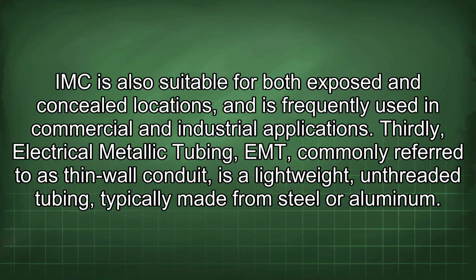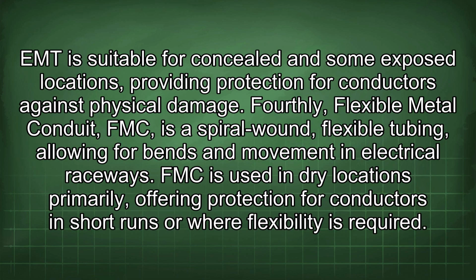IMC is also suitable for both exposed and concealed locations, and is frequently used in commercial and industrial applications. Thirdly, electrical metallic tubing, EMT, commonly referred to as thin wall conduit, is a lightweight, unthreaded tubing typically made from steel or aluminum. EMT is suitable for concealed and some exposed locations, providing protection for conductors against physical damage.